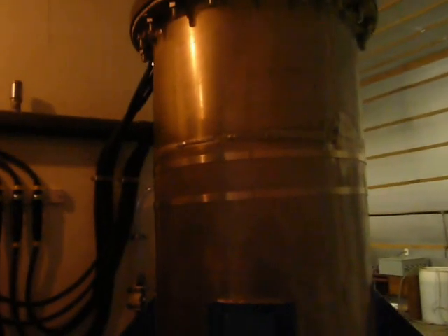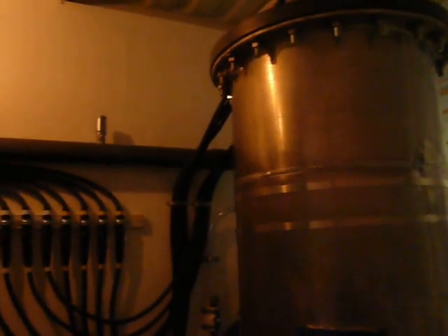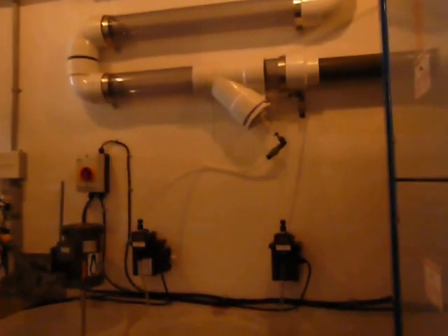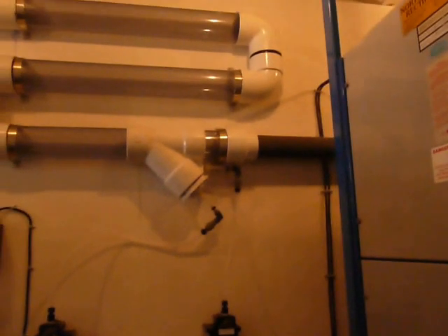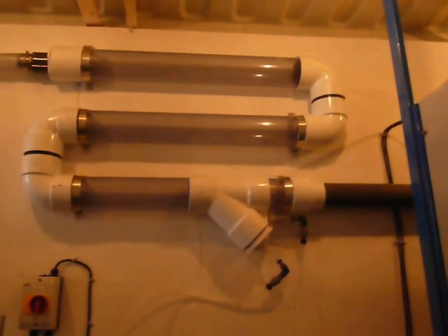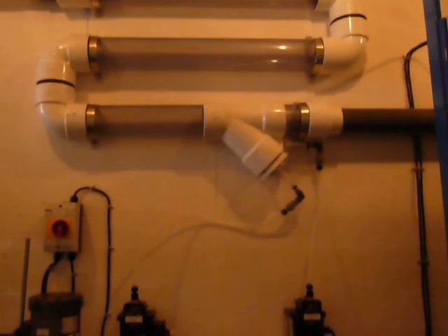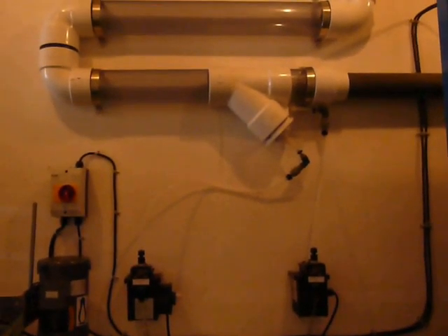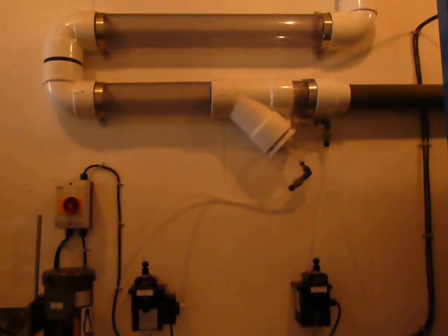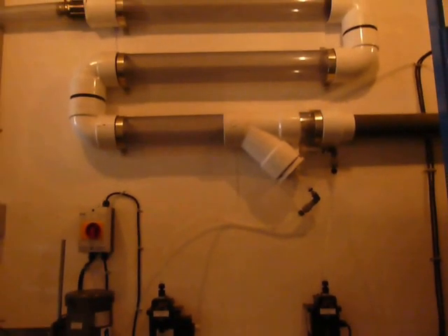So the raw water enters through the piping here and meets the ozone and the other oxidants, which work to reduce the COD levels and also separate the suspended solids from the liquid phase. Once that happens, the water enters the static mixer where we inject a combination of coagulants and flocculants, or one of the two as the case may be. Depending on the effluent, we can adjust the recipe.